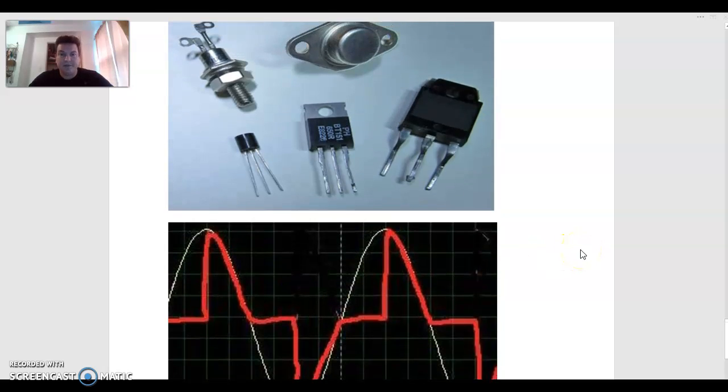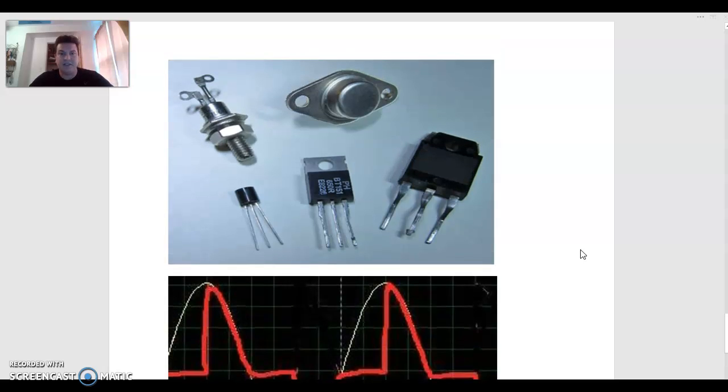Two things. One, with just one standard SCR in an AC circuit, it's going to act as a rectifier, which is exactly what it is, a silicon controlled rectifier. It's made up of a few PN junctions, which we talked about with diodes, and the gate is tied into one of the P-type or N-type materials, typically the P-type. When it was used in the earlier VFDs, it's a little bit better at controlling voltage in a DC circuit.